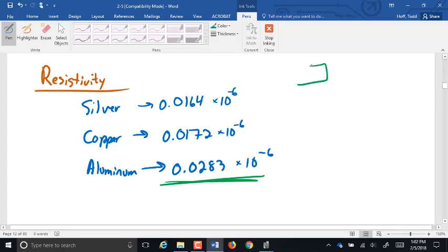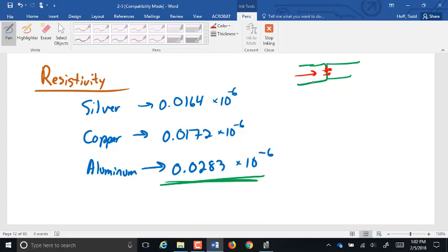And once the aluminum wire cracked, what's going to happen when you push electricity through it? Well, right here, there's going to be a spark, right? As long as that's close enough together, the electricity is going to jump. It's going to spark across. Well, what happens when electricity sparks from one conductor to another? It gets really hot. That extreme heat eats these ends, and they start to crumble. And what will happen is the spark has to jump further and further to get across that gap created by the crumbling aluminum, and eventually it sparks big enough to light something else on fire. So aluminum wiring was a huge fire hazard.